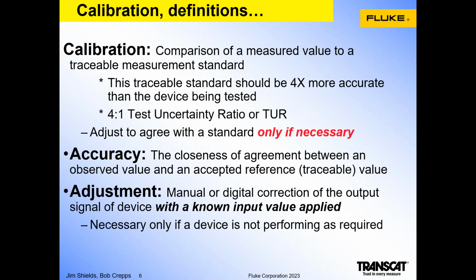And in the case of this intercomparison, in the event that the device that you're testing is found to be out of tolerance, you adjust to agree with the standard if necessary. It is possible to perform a calibration and intercomparison and find the device within tolerance and not have to make any adjustments at all and still perform a calibration. So a calibration can be performed with or without adjustment, but the adjustment is not necessary. It's only necessary if it's necessary to pull the device under test to agree with the standard within the allowable deviation.